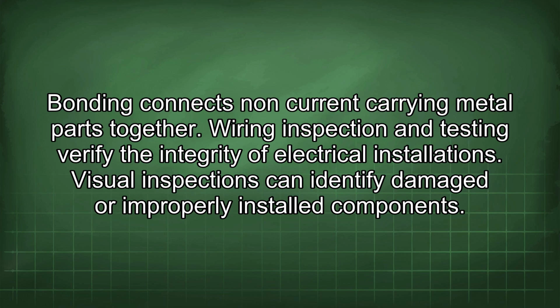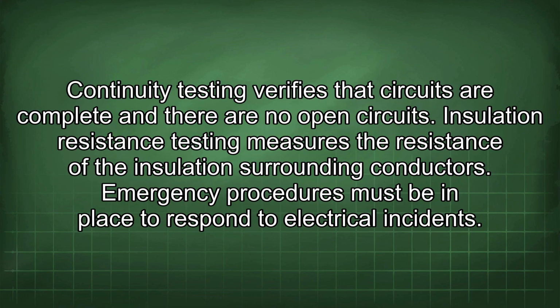Wiring inspection and testing verify the integrity of electrical installations. Visual inspections can identify damaged or improperly installed components. Continuity testing verifies that circuits are complete and there are no open circuits. Insulation resistance testing measures the resistance of the insulation surrounding conductors.